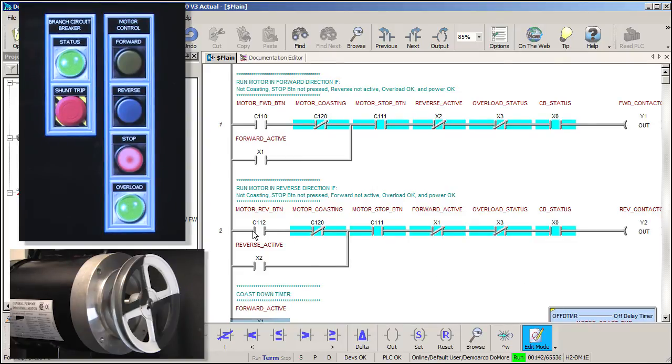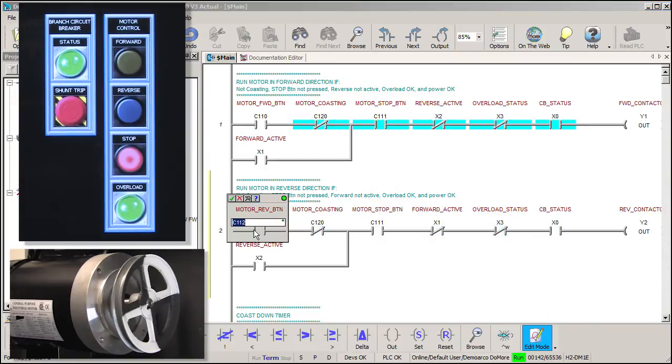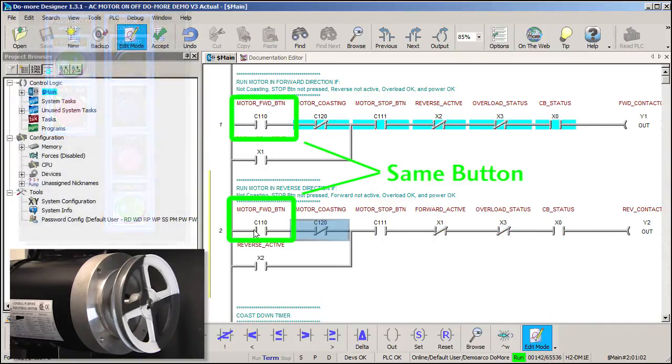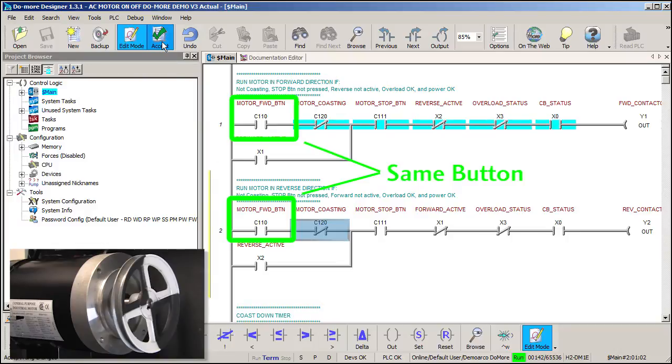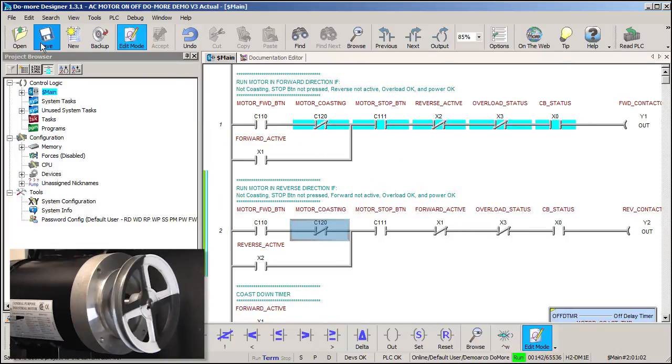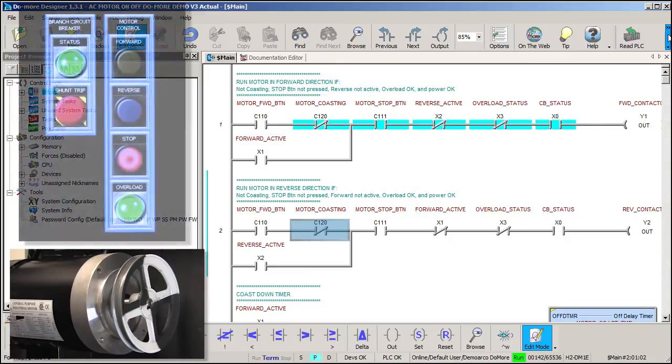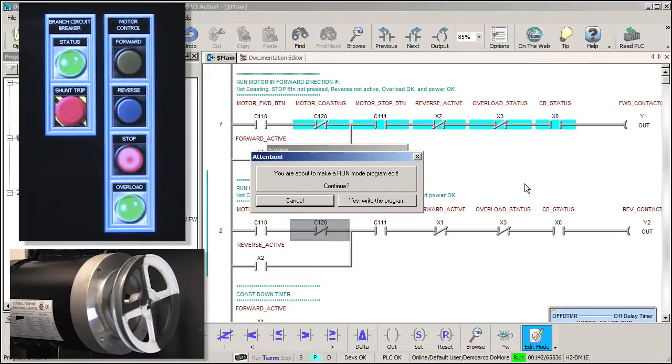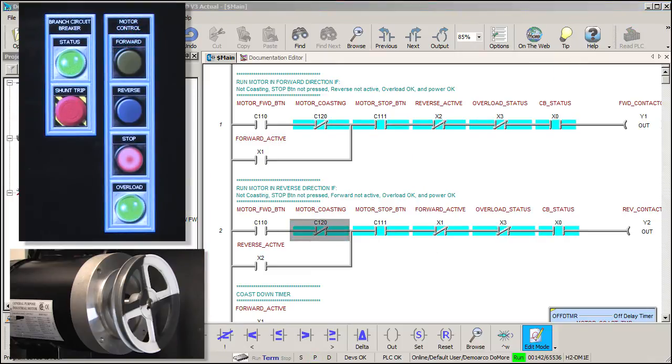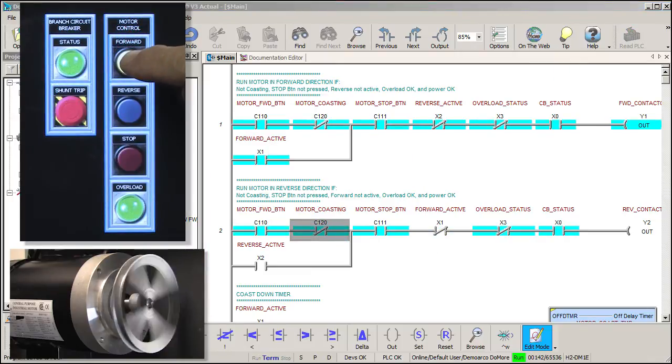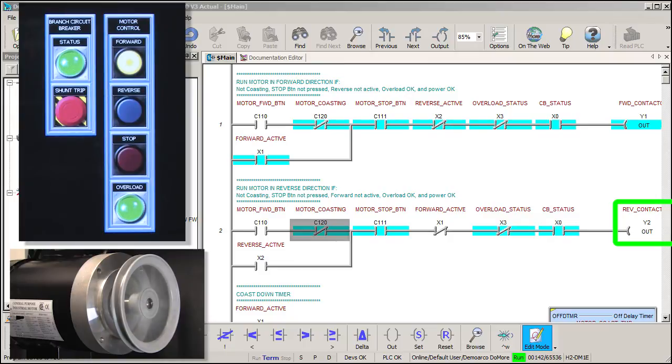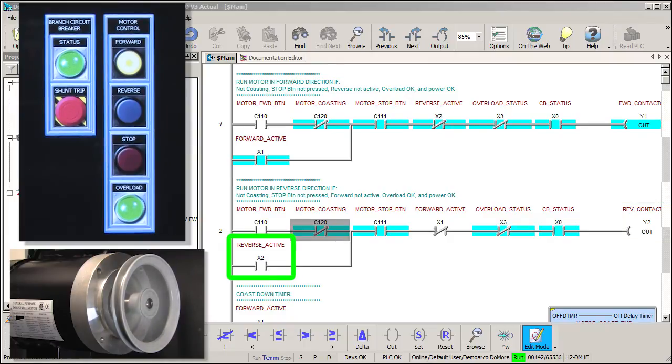Let's prove it. Let's engage both contactors on the same forward button press. Now they are guaranteed to start at exactly the same time. Let's accept that change and write it out to the PLC. Sure enough, if we press the forward button, both circuits light up, but then the reverse circuit turns back off because the mechanical interlock wouldn't allow the reverse aux contact to close.